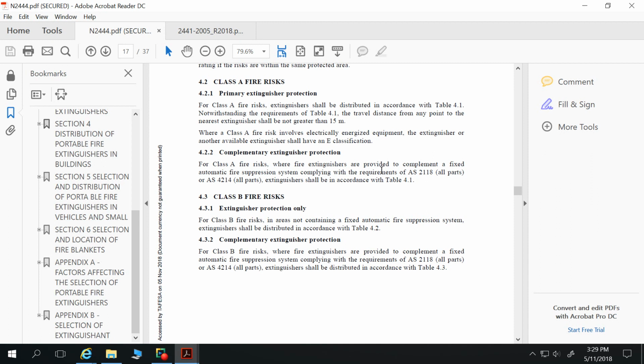For Class A fire risks, extinguishers shall be distributed in accordance with Table 4.1. The travel distances from any point to the nearest extinguisher shall not be greater than 15 metres. So if we don't have hose reels, then we do have to start having a lot of fire extinguishers dotted about the place, because in some instances, like a warehouse, you've got lots of 15 metres happening about the place. So plenty of extinguishers.